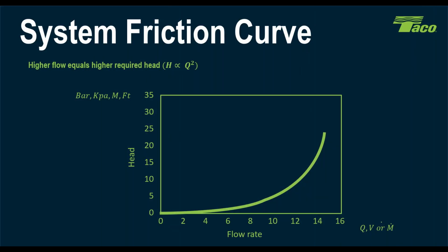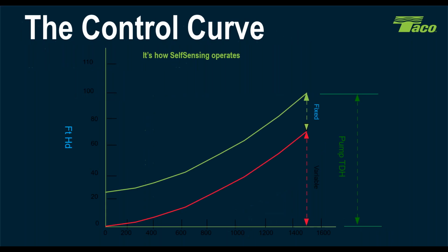So if we look at this, we understand that with a system curve, as we increase the flow rate, we increase the head that is required in the system because we're increasing the frictional losses moving water through the piping system and through all the components in the system. And the control curve is really how self-sensing operates. This is a representative curve for a pump. The green dashed line on the right-hand side is the pump total dynamic head. That is the head that you've calculated is supposed to be there for the design flow rate.